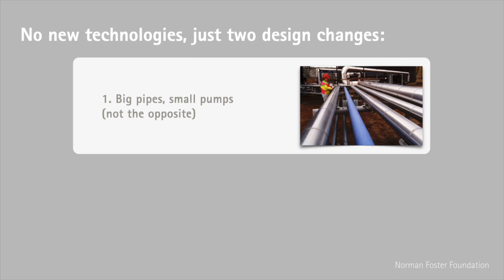So how fat should the pipe be to optimize the friction? Well, the textbooks say to make the pipe just as fat as will repay its extra cost over the years from the saved pumping energy. But that's wrong because it leaves out the capital cost of the pumping equipment.